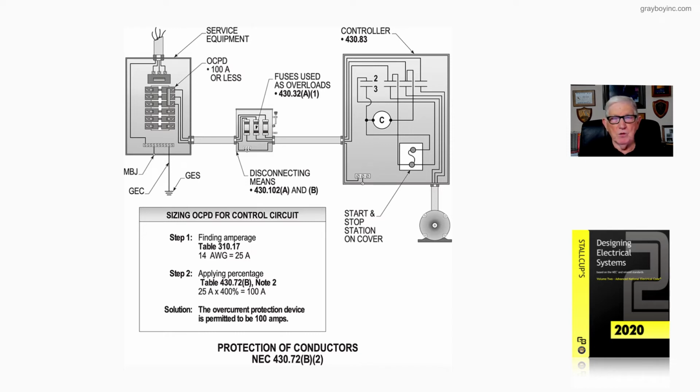But in the 2020, then don't forget, it's free air, and you can see in the contactor there that those conductors are in free air. They're not inside a raceway system.